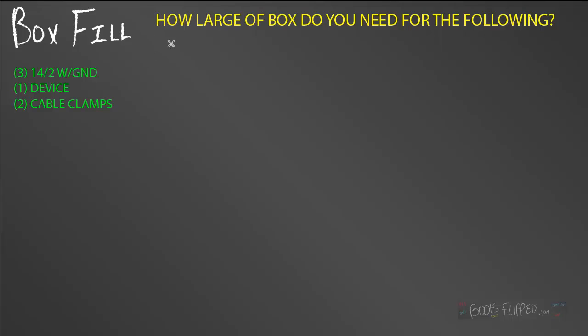In this box, I want to know how large of a box I need. So, I have three 14-2s with a ground, one device, and two cable clamps in this box. Well, let's remember that number 14 is from our table. Number 14s, they equal two cubic inches per conductor. So, let's get into our calculation. Follow along. You can do it however you want, but I try to stay organized with my calculations. That way, I don't lose something in the process.